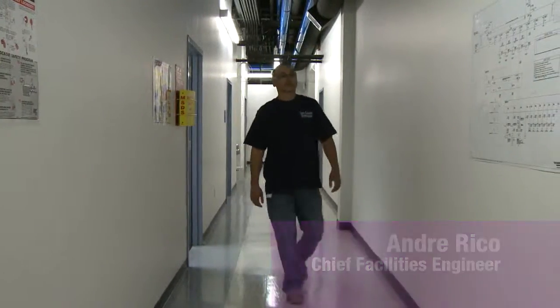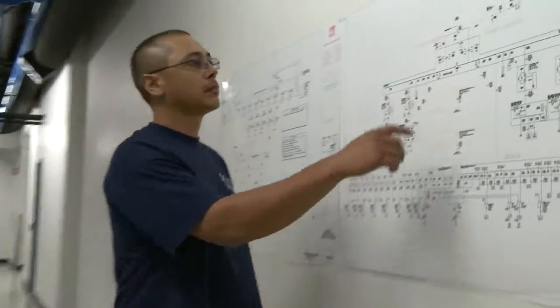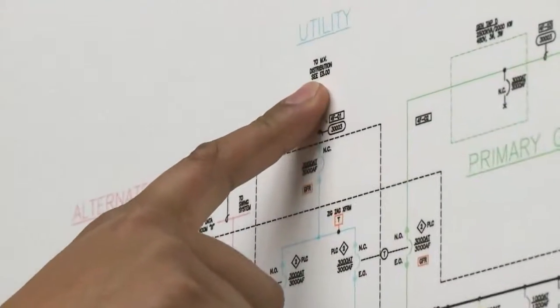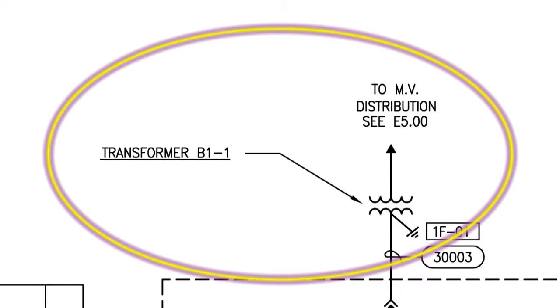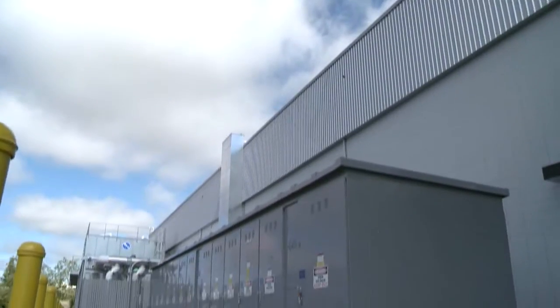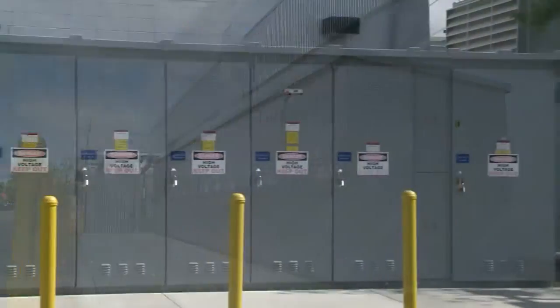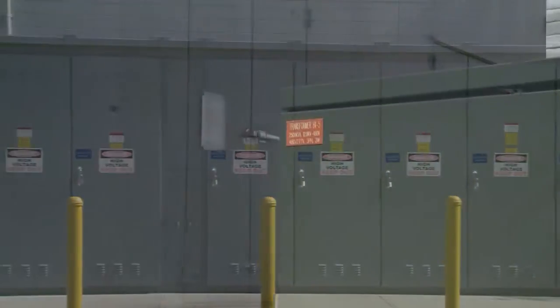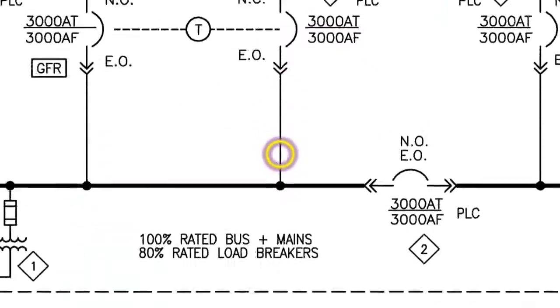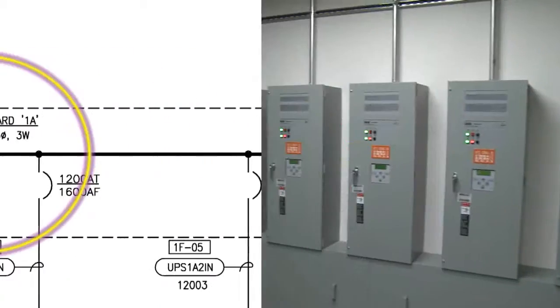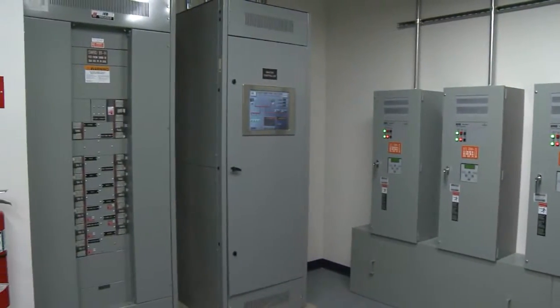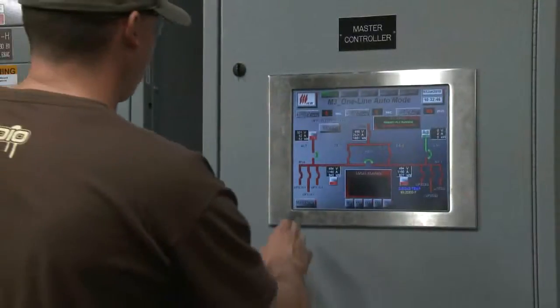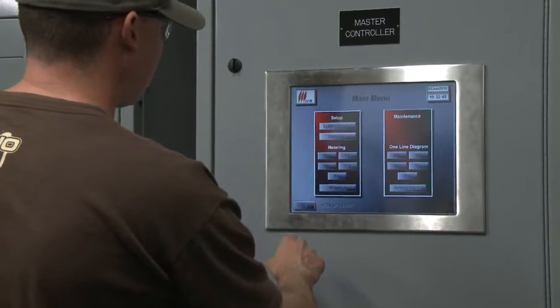Let's say you're an electron traveling through the data center. Where would you go? How would you get there? Let's find out. The primary switch gear, or PSG, is where the utility service enters the facility. The PSG is served by two separate utility services for redundancy. Medium voltage transformers convert 12,000 volts to 480 volts, which is delivered to the main switchboards as usable power. Here you can see one in an electrical room where the main distribution and power systems are located.